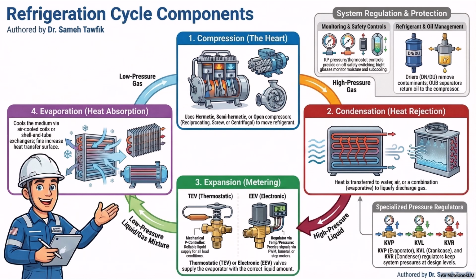And we can't forget the OUB oil separators. What do those do? Well, when a compressor violently pumps gas, a little bit of its lubricating oil always gets carried away in the flow. The oil separator catches that oil from the hot discharge gas and immediately returns it to the compressor crankcase. So the moving parts don't dry out and seize up. Exactly. Okay, here's where I need to push back a bit.